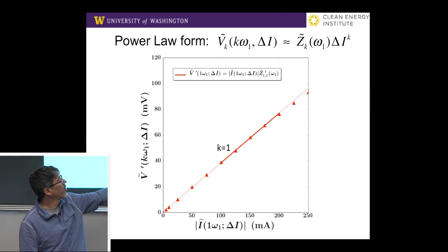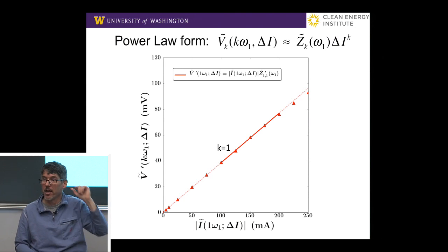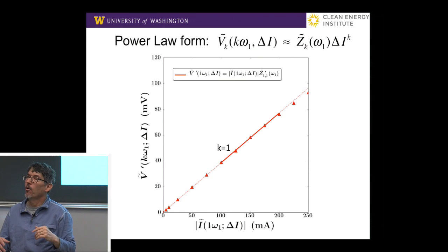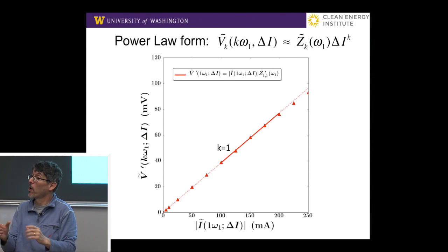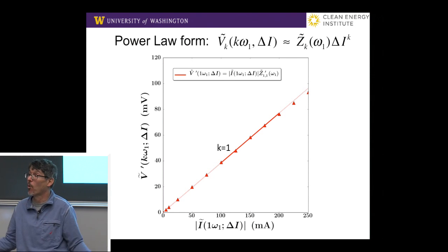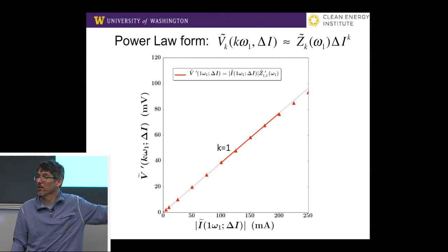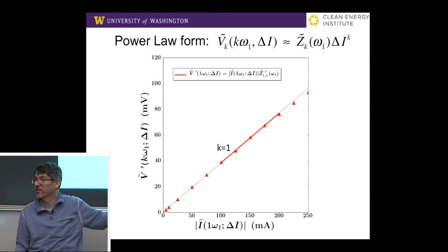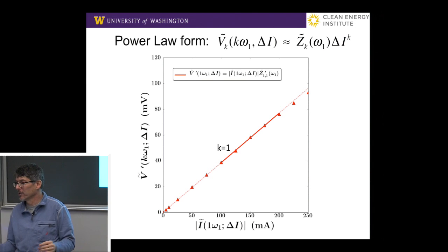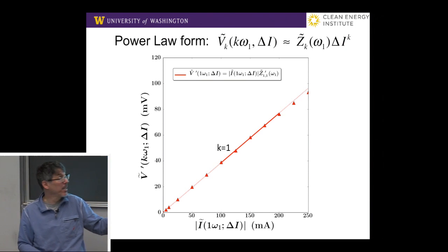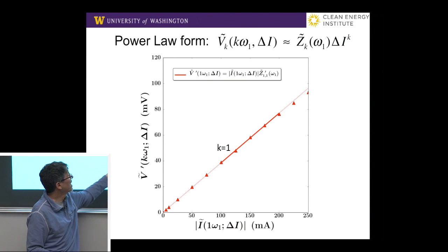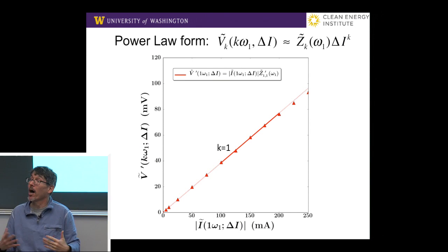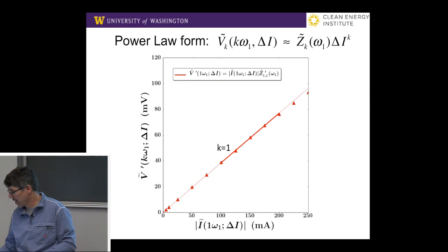in this range of 100 milliamp modulation to 200 milliamps, just because when we go to higher frequencies, our signals are smaller, and that gives us good resolution over a wide range of frequencies. So it looks like here we could go to much lower modulations, at least for the linear component. And most people who do linear impedance are doing it down in this regime. But we want to excite nonlinearity, so that's fine for us.